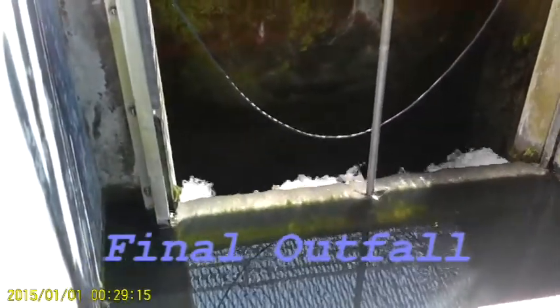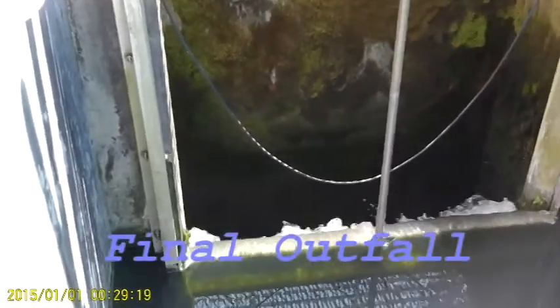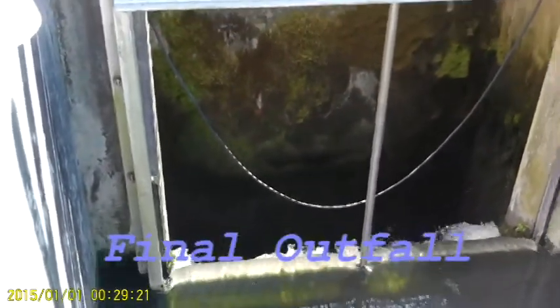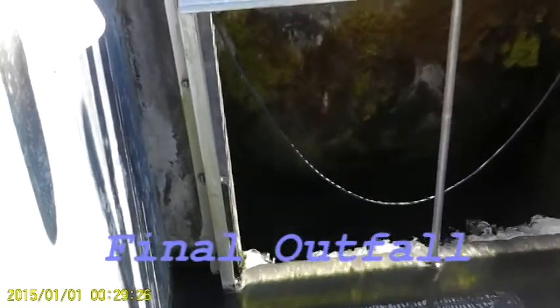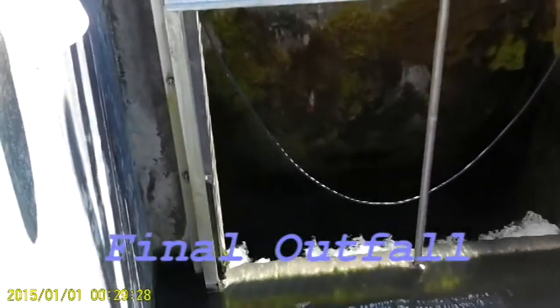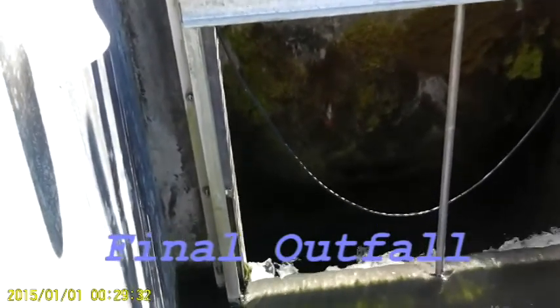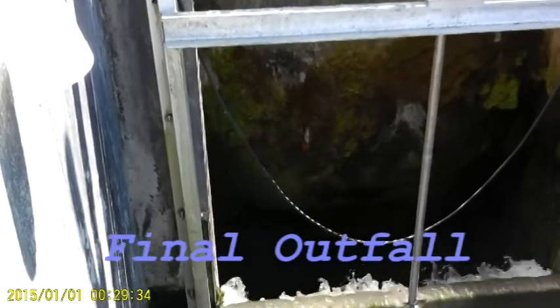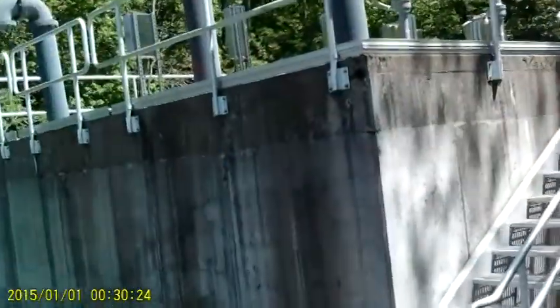This water right here is good quality effluent, less than 10 milligrams per liter total suspended solids, biochemical oxygen demand lower than 10 milligrams per liter, low levels of phosphorus, 0.3 milligrams per liter total phosphorus, 3 milligrams per liter or less of ammonia, and various metals, and low levels of E. coli. In a flood condition, we have to pump it into the river.